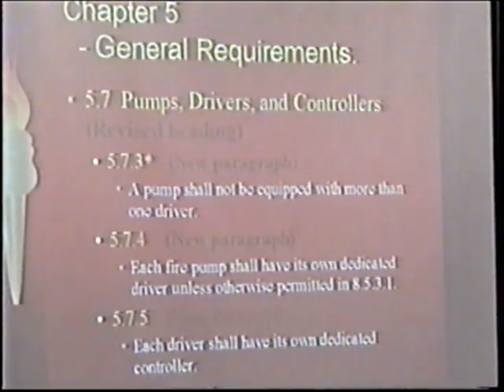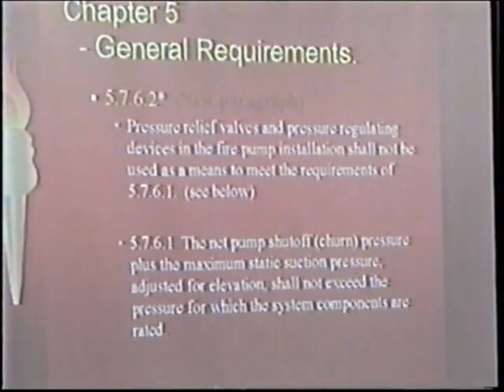I don't know about each driver having its own dedicated controller. I'm not sure if that was ever an issue. I don't know if it's ever been an issue, but I could see where there are some people now, especially with the VFD controllers, that would consider controlling multiple pumps with one larger VFD controller. It's done all the time with VFDs in regular industry, so I could see some electrical contractor trying to do that.